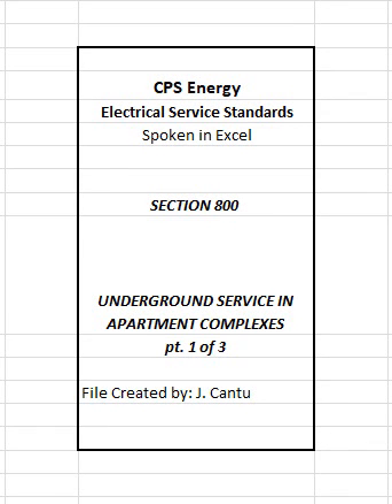Section 800 Underground Service in Apartment Complexes. 801 General. This type of service is designed for apartment complexes where all utilities are installed underground. A service lateral installed underground in conduit from a CPS Energy transformer or riser pole to meter loop on customer's building or structure supplies service.